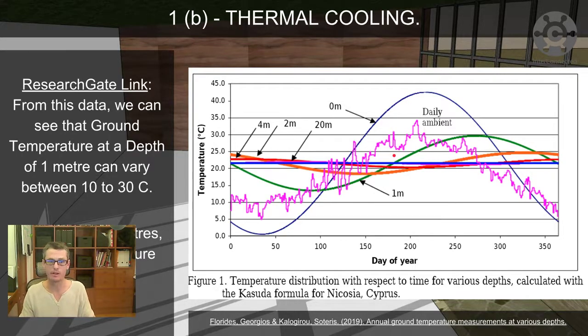But the interesting thing about this is there's a lag. The lower down you go in the ground, the more time it takes for the sun to heat that ground up. So at a meter there, the green line shows it well. Outdoor temperatures here are about 40, or ground temperatures here are at 0 meters on the blue line, are about 42 degrees. You look at the green line, the curve is lagging behind it as the ground takes time to warm up. So even though at a meter depth you still get less variation in the ground temperature, it's still only around 25, 26 because the ground hasn't warmed up yet. It's taking time to catch up with summer to warm the ground up.